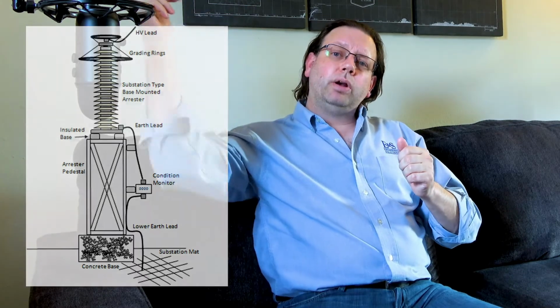So we have a power line coming in. Let's say we have a 220 kV power line coming in, and on phase A we have a lightning arrestor that's designed to short to ground should the voltages go too high above our line voltage. It'll dump it to ground. And there's one and only one ground wire tied to that lightning arrestor and that post.